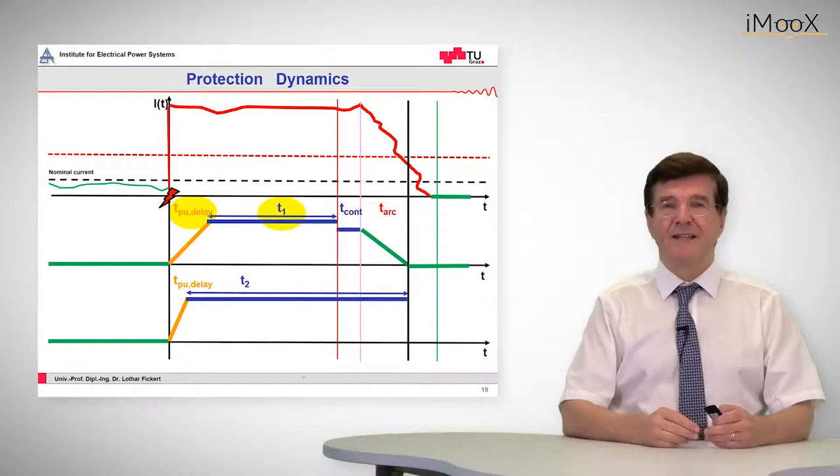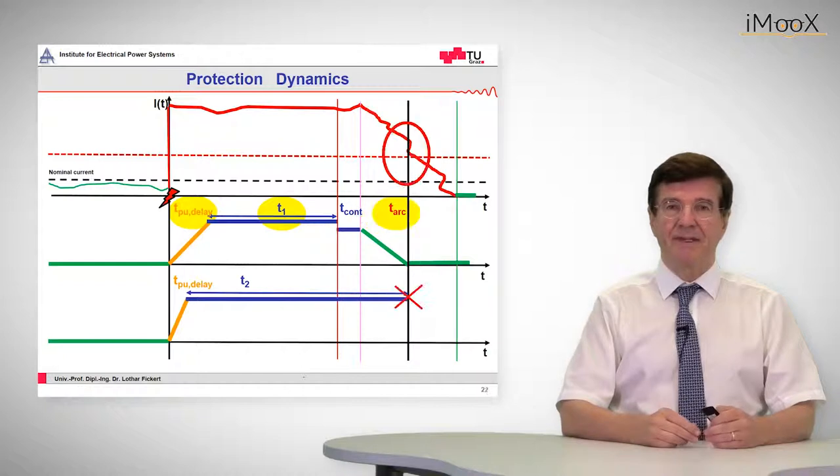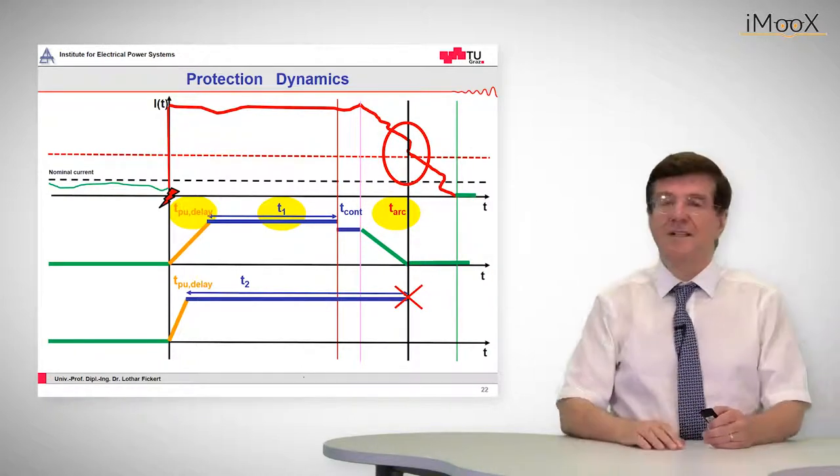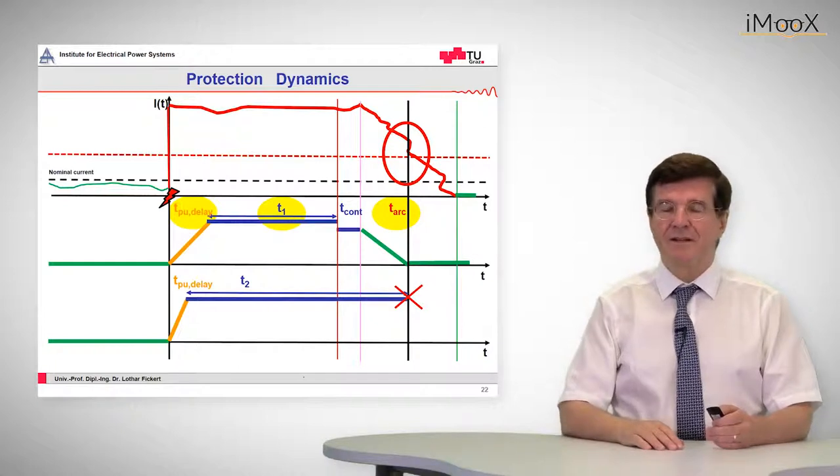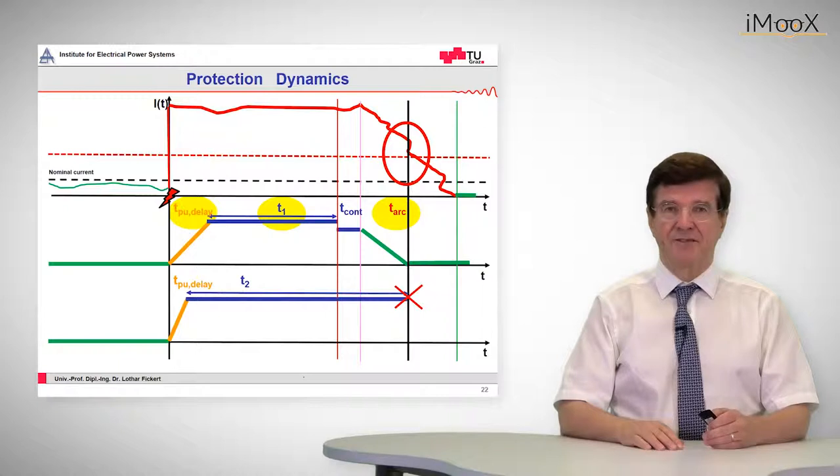Also the retarding time, the grading time may be increased and that means that again the whole procedure lasts longer and also the contactor and the arcing time may increase. And that will lead, as is indicated in the red circle, to an overlap with the intended tripping time of the upstream relay T2.